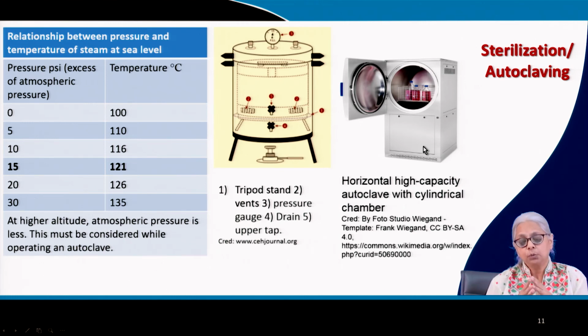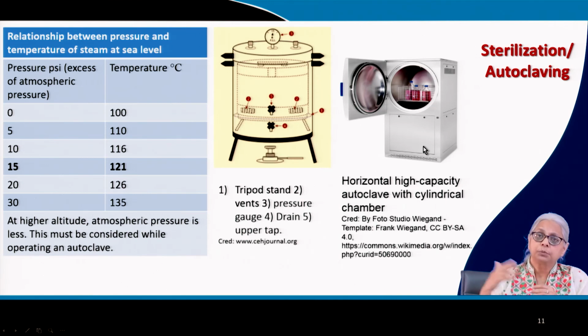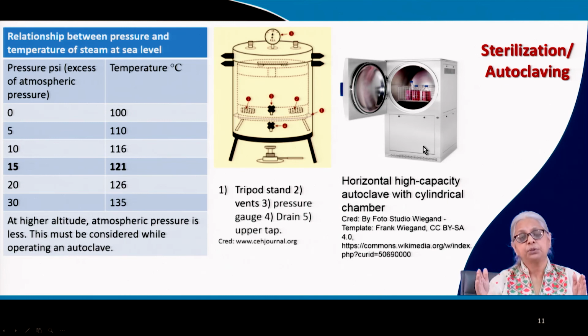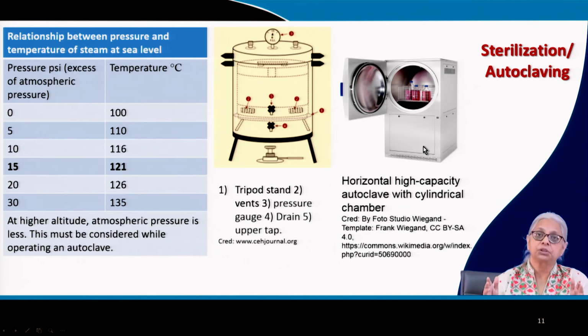Now, a very important point in autoclaving is that the entire cycle, in practical terms, from the point of closing the door to the point when it is safe to reopen the door, can be anywhere from 1.5 hours to 3 hours or so. But the actual autoclaving time is 15 minutes, because it takes a fair amount of time for the steam to build up. You have to maintain the steam and pressure for 15 minutes to ensure that you get complete sterilization of the equipment, both the dry goods and the wet goods.